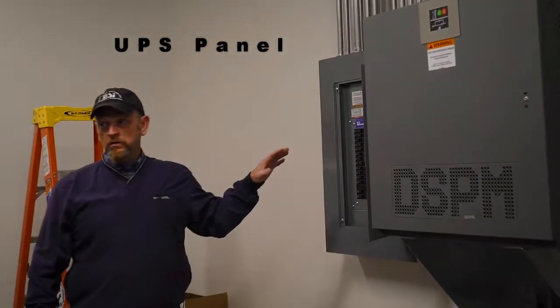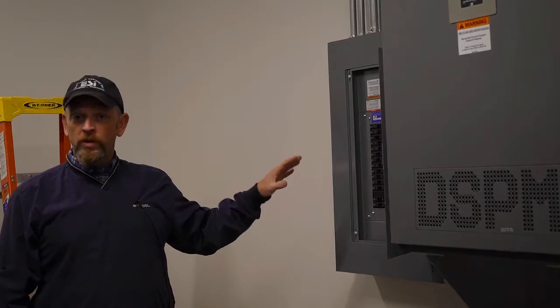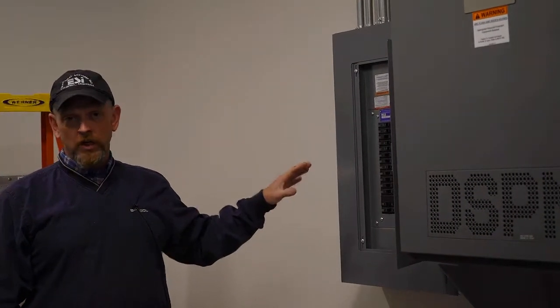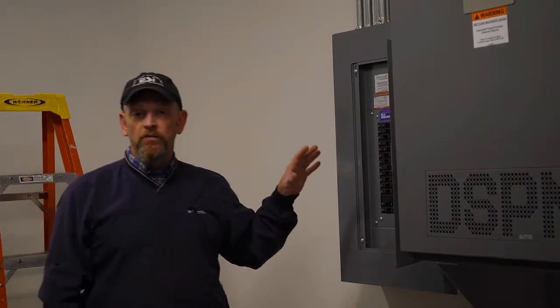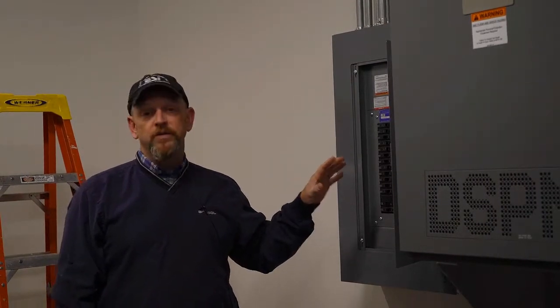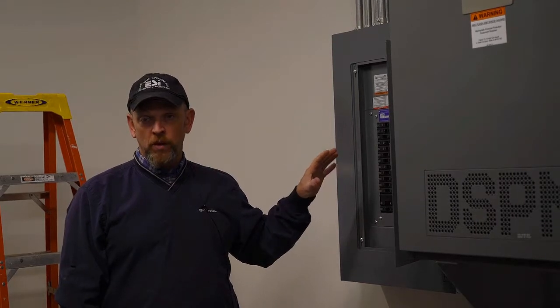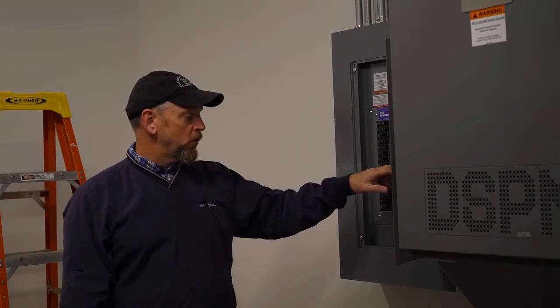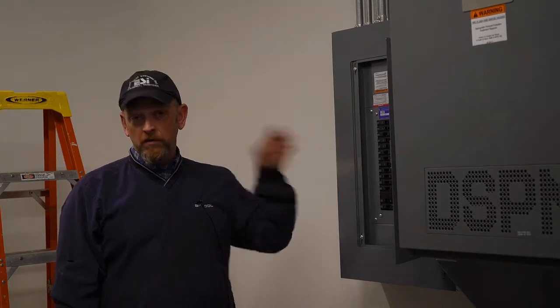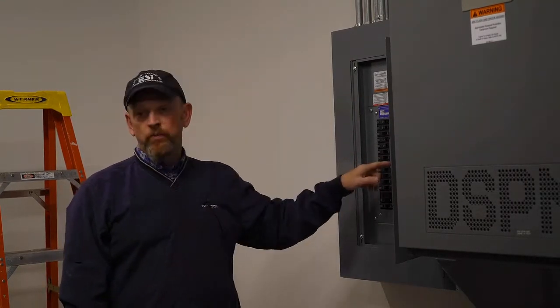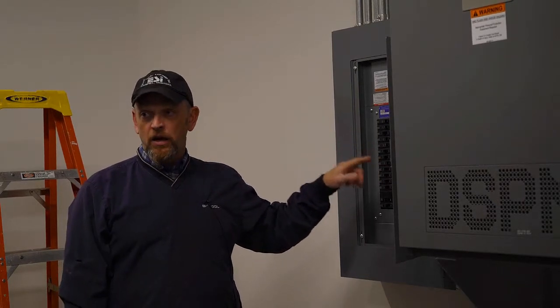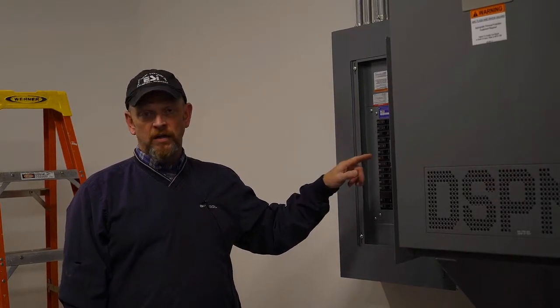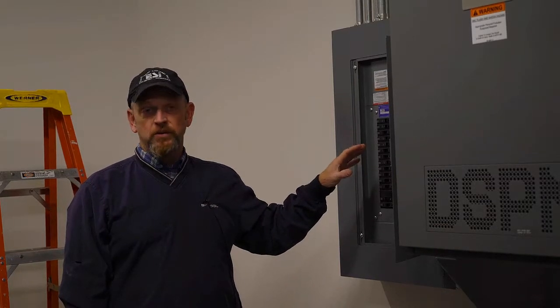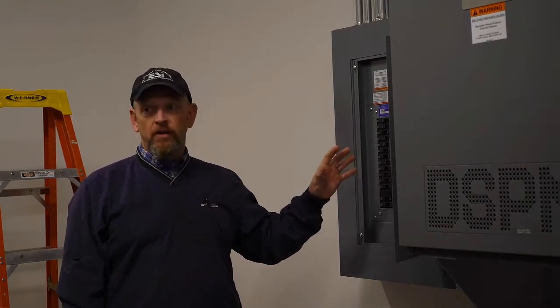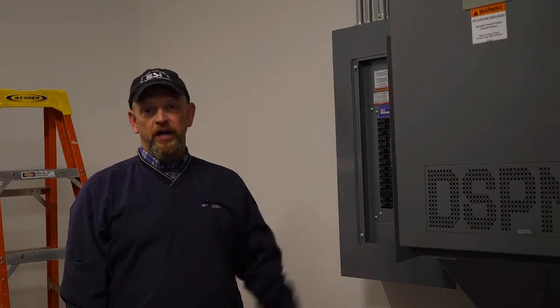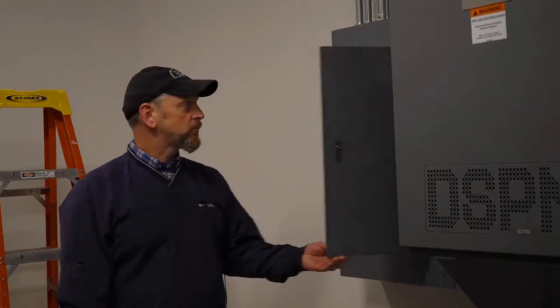all of the point of sales are on this panel. So if the point of sale goes down, the UPS panel is where you need to go. There's also a couple of offices, the controller's office, that have UPS circuits on them as well. One thing that you'll need to note on here is that the fire alarm panel, which is right behind us, is fed from this panel. That needs to stay on. It should always stay on unless something catastrophic happens and it has to be shut down. If you turn that off, the whole system's going to go down, and that'll notify the fire response system.